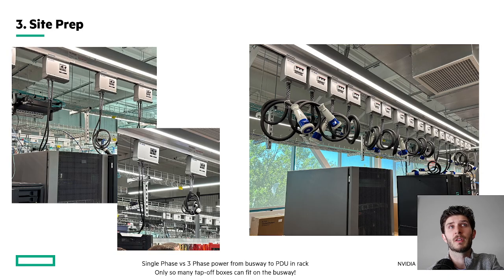For those interested in learning more, on the left side of the screen I have a picture of a single phase drop from the busway to the PDU in the rack, and on the right side a picture of a 3-phase drop. Both of these are actually not the 5-wire setup I just described as more modern, but it's meant to demonstrate that for a given busway, there's only so many tap-off boxes you can fit on there.